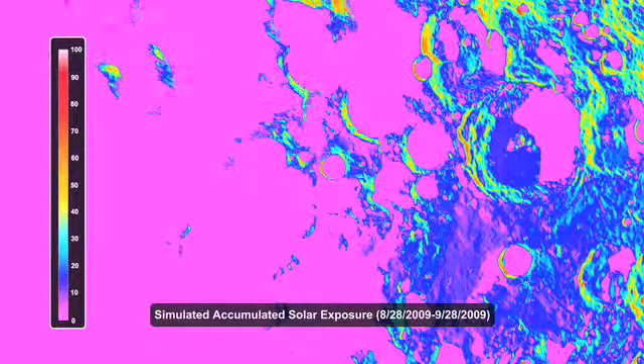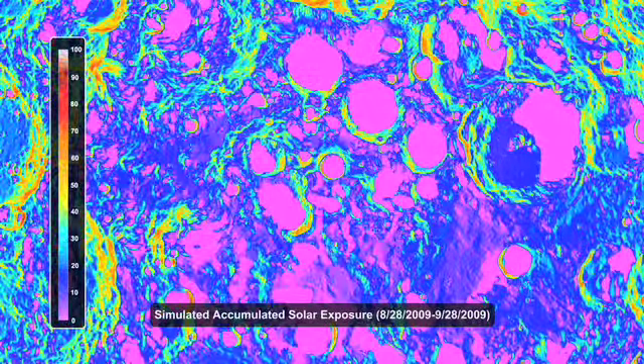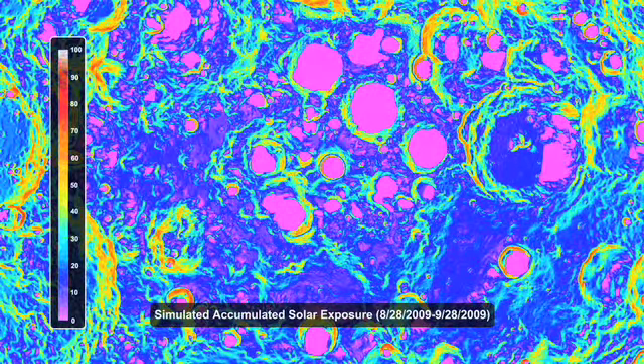It has 2 telescopes, and radiation comes into both telescopes and then is focused on a pair of detector planes that contain a bunch of filters that filter the radiation, and then we get a series of measurements in 9 spectral channels. 2 of these are devoted to reflected solar radiation, and these are sensitive to the total amount of light that your eyes might see in the visible part of the spectrum. The remaining channels are in the infrared part of the spectrum, at wavelengths beyond those that the human eye can see. And these pick up radiation that's emitted from the moon, which increases as a function of how hot the surface of the moon is.